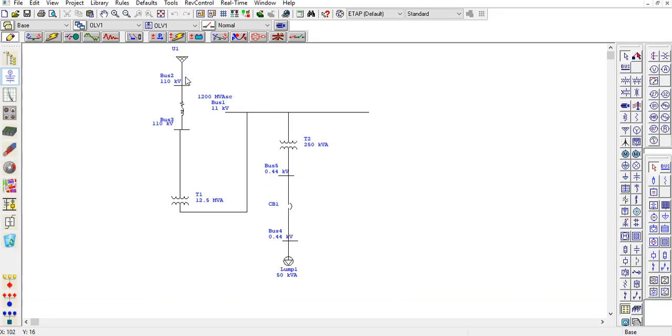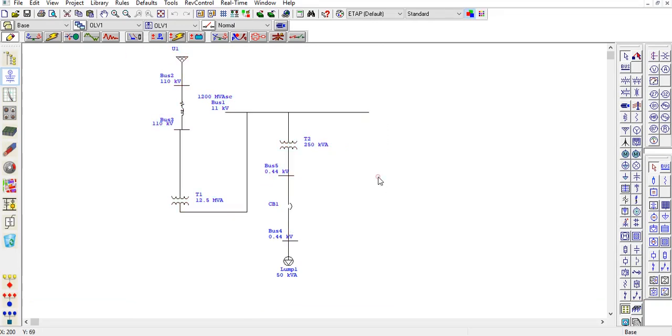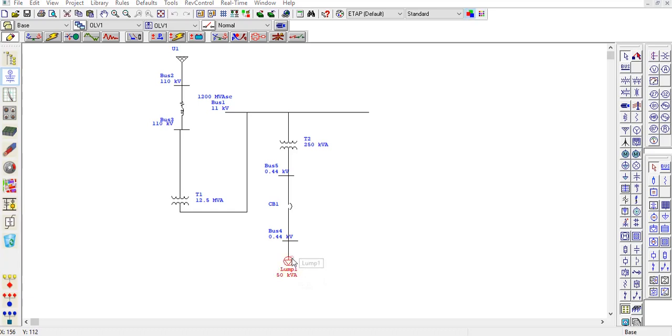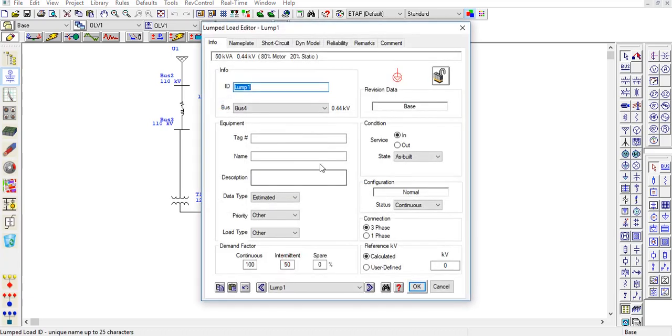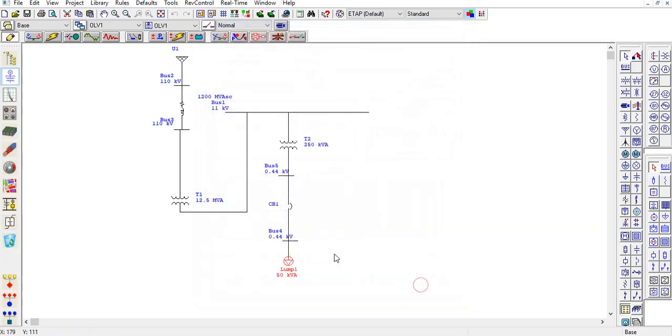I showed you how to make a single line diagram for the arc flash analysis. For your review, I added a circuit breaker in the last video because the arc flash analysis needs a protective element like a breaker. I set the current from the full load ampere of the load that you can see from the nameplate. The load current was 55 ampere, so I set it for nominal current of 70 ampere, which was the most close to the actual current of the load.